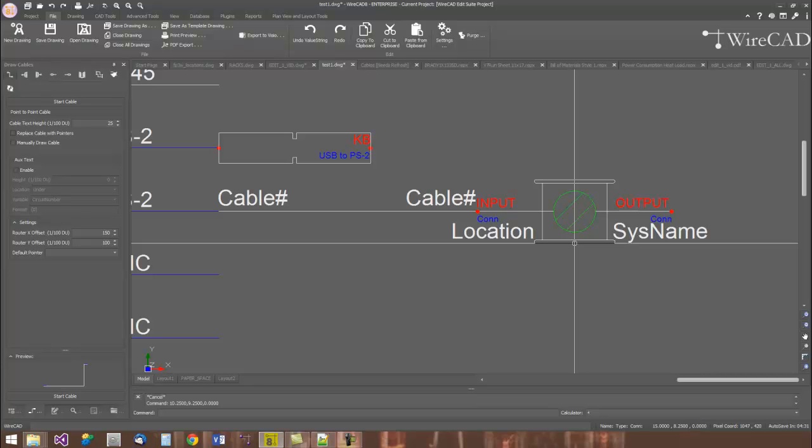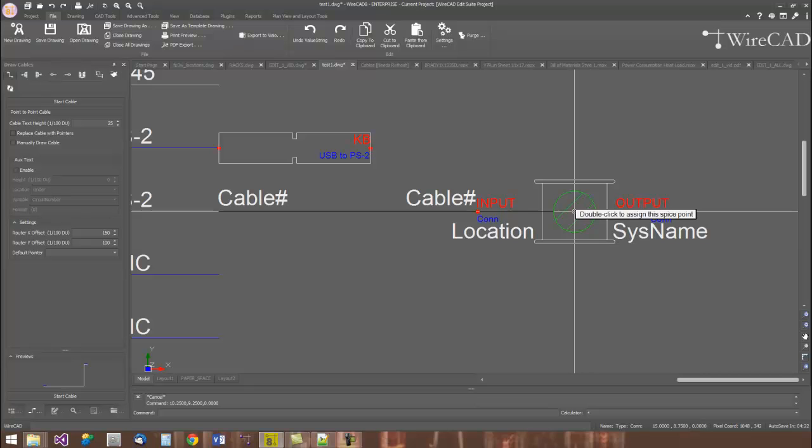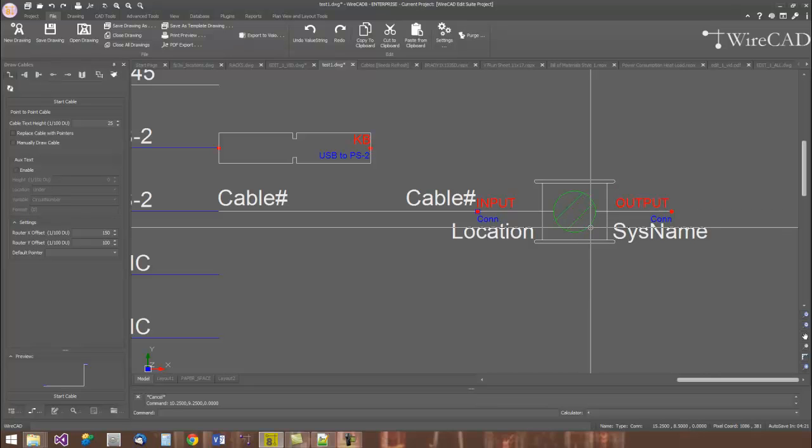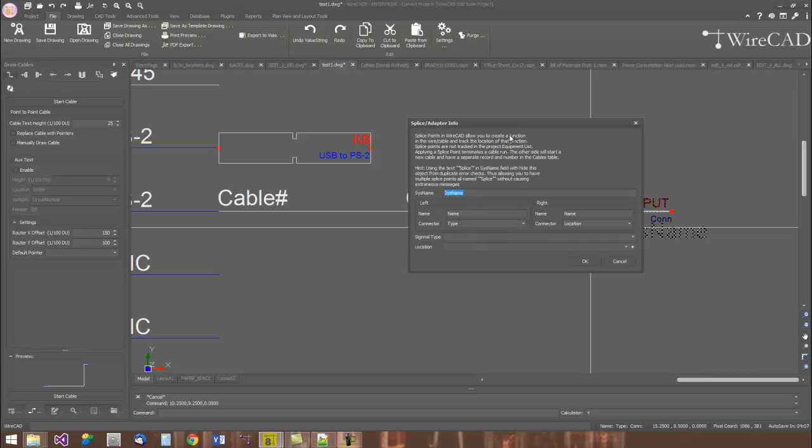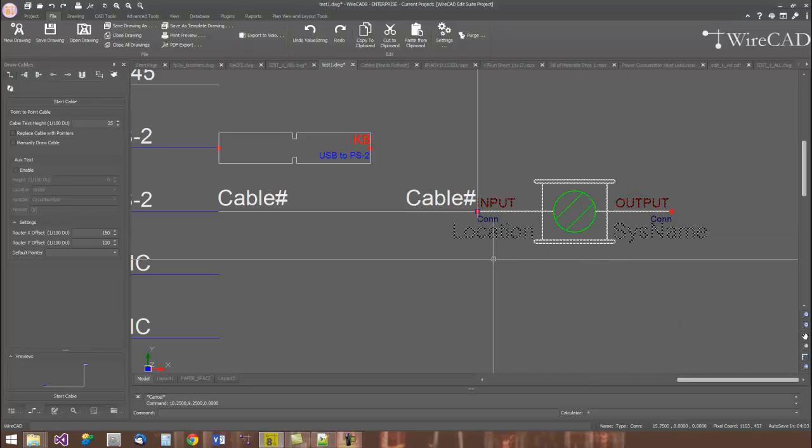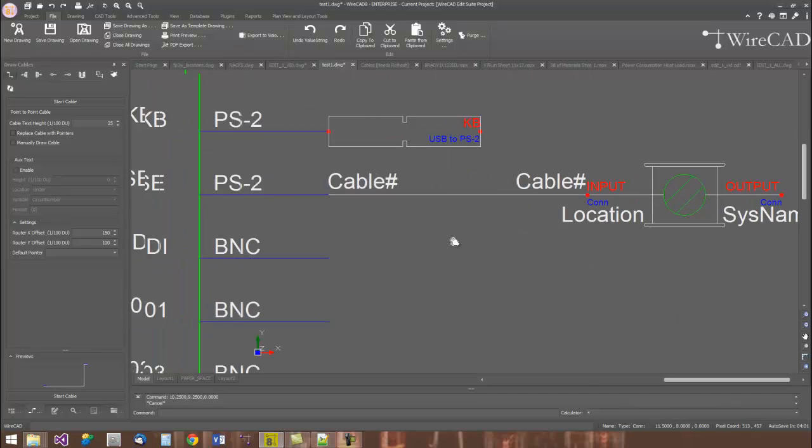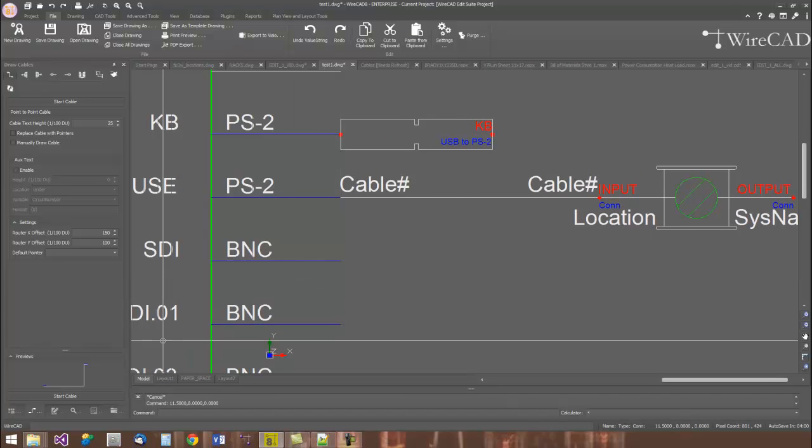WireCAD splice points don't have to be tracked. If you simply name them splice or it contains the name splice, then that particular item won't be tracked in the overall equipment list. Double-click the item to name it and give it a port name and type and connector types. That information will then go into the cables database as we assign cables.